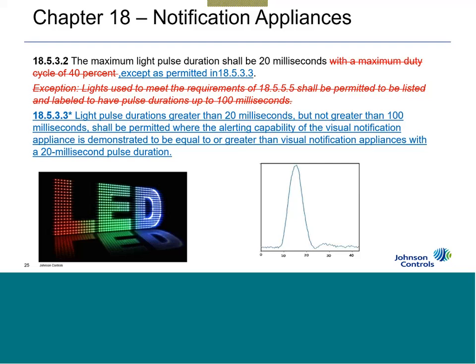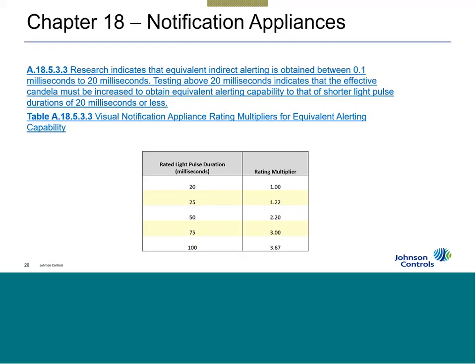So they petitioned NFPA and said, look, we developed these devices way before you changed the standard. I spent a lot of money getting them listed, engineered, out to market. What do I do? So NFPA said, how about we give you a derating ability? So you may have heard about LED strobes needing to be derated. Well, that's true, depending upon your manufacturer. So it all starts with the 20 millisecond or less. If you have an LED that fires, hits peak intensity, and discharges below 20 milliseconds, you're fine.